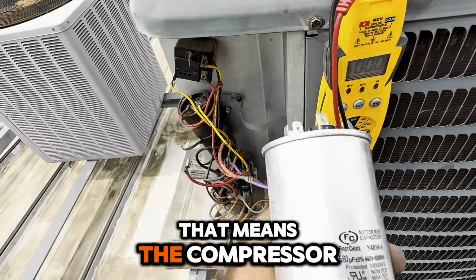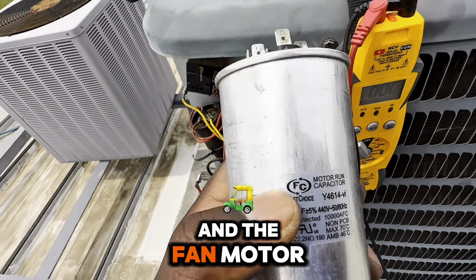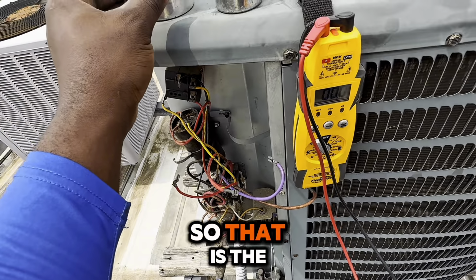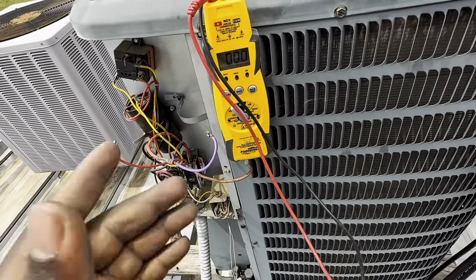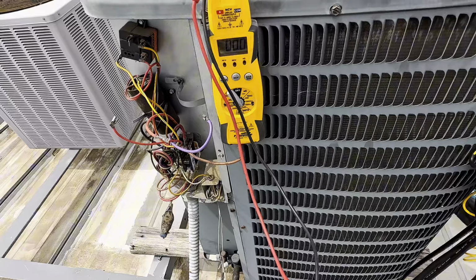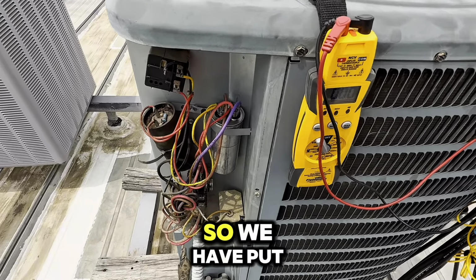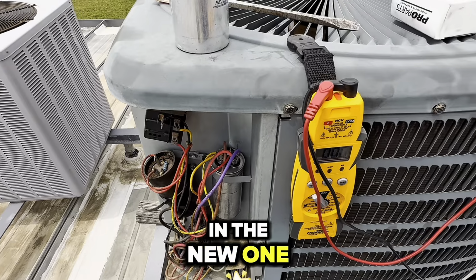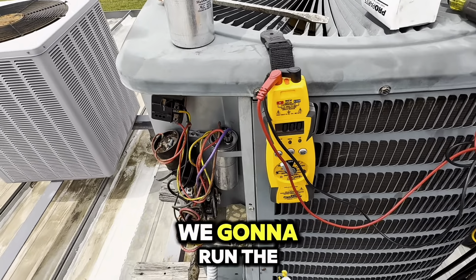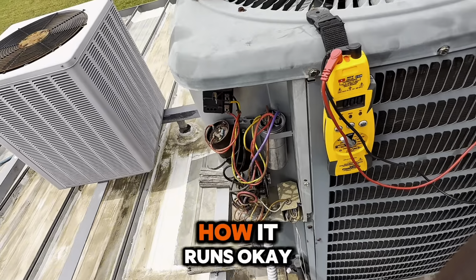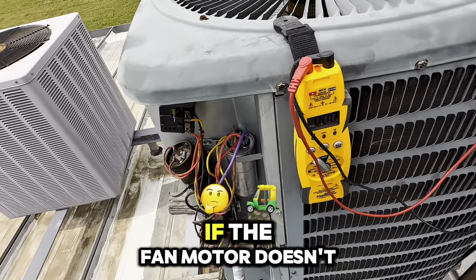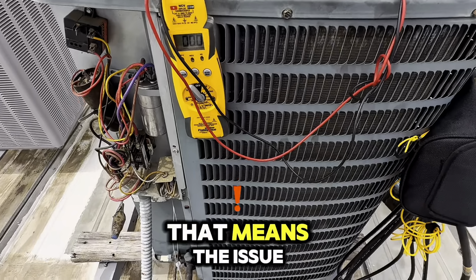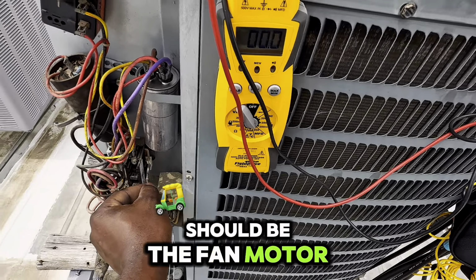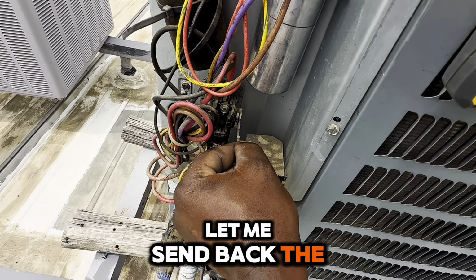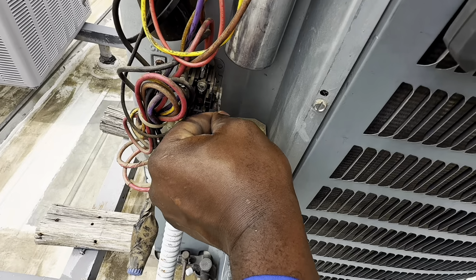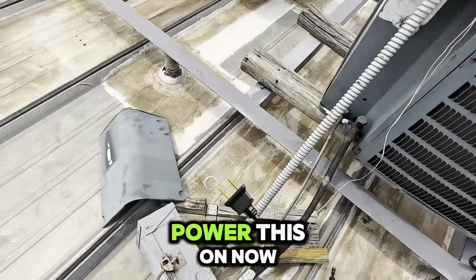We're gonna replace it. That means the compressor takes 60 and the fan motor takes 5. So that is the situation here. We're gonna replace the capacitor, and I believe the unit should be good to go. So we have put in the new one, and we're gonna run the unit now and see how it runs. Okay, if the fan motor doesn't run again, that means the issue should be the fan motor. Let me send back the low voltage power, and then I power this on now.